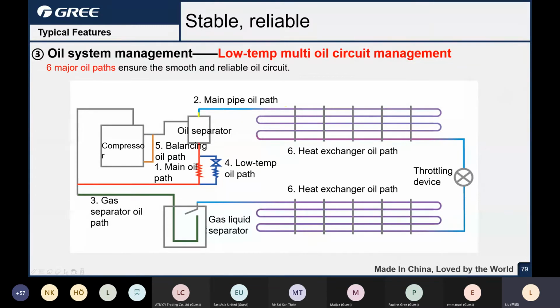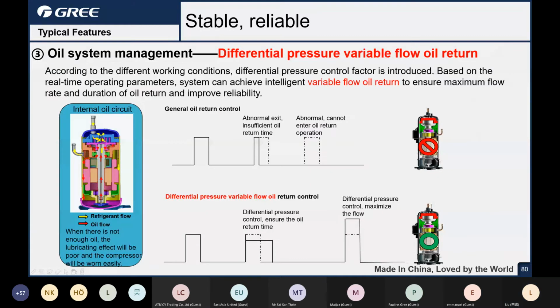Next one is the main pipe, the copper pipe. We will know that the copper pipe and gas liquid separator, there is also an oil return path for the compressor. So actually, the unit has 6 major oil paths for the oil circulation and return. And for the oil return, how the compressor can get oil return. Okay, let's have a look at this comparison. For ordinary oil return, you can see here.